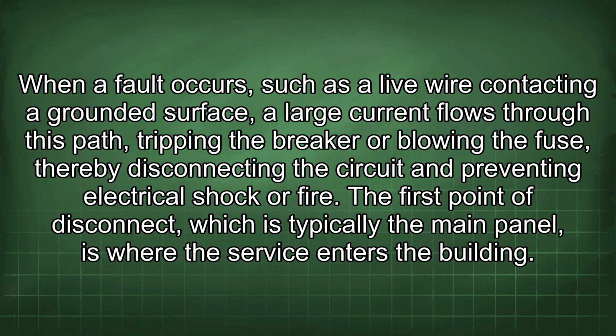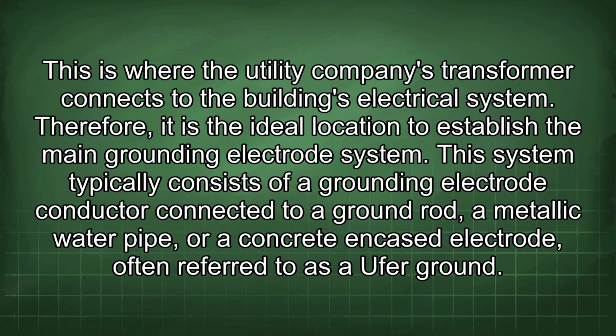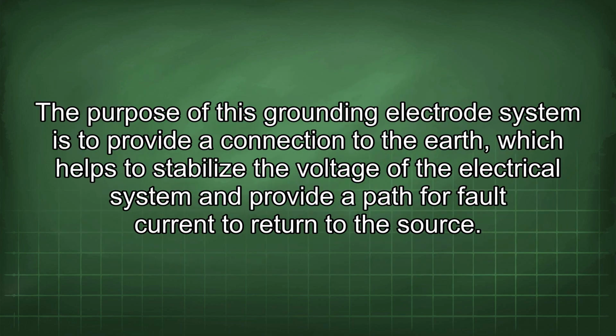The first point of disconnect, which is typically the main panel, is where the service enters the building. This is where the utility company's transformer connects to the building's electrical system. Therefore, it is the ideal location to establish the main grounding electrode system. This system typically consists of a grounding electrode conductor connected to a ground rod, a metallic water pipe, or a concrete encased electrode, often referred to as a UFER ground. The purpose of this grounding electrode system is to provide a connection to the earth, which helps to stabilize the voltage of the electrical system and provide a path for fault current to return to the source.